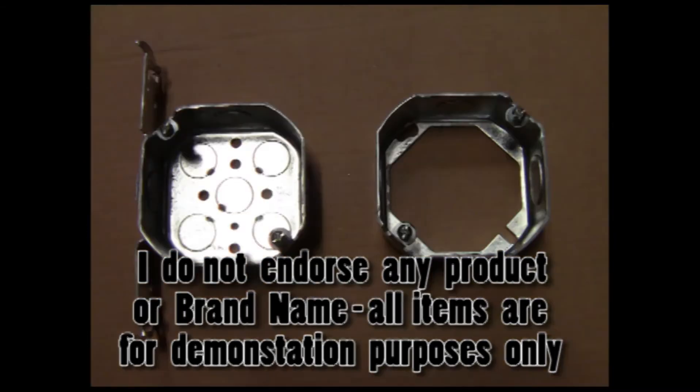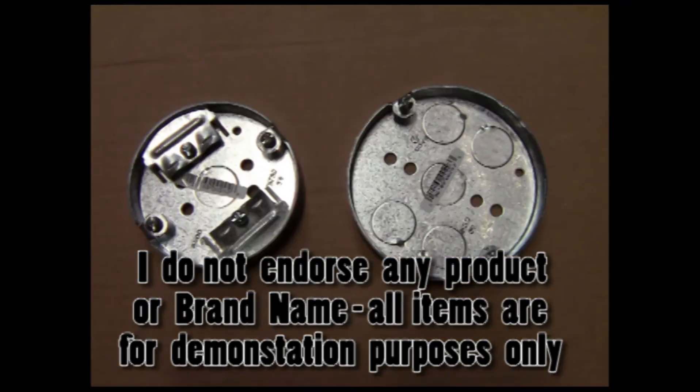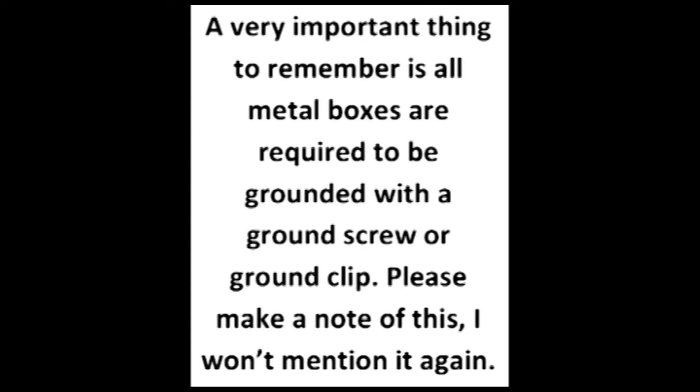A very important thing to remember is all metal boxes are required to be grounded with a ground screw or ground clip. Please make a note of this. I won't mention it again.